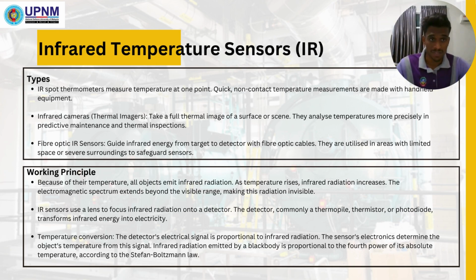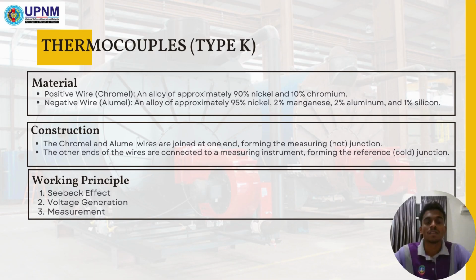Now let's not get deep into it because there's another important transducer which we're going to use for the project. Now this is the transducer we're using for the project, the thermocouple type K. For the positive wire we are using chromel, an alloy of approximately 90% nickel and 10% chromium. And for the negative wire we are using alumel, which is 95% nickel, 2% manganese, 2% aluminum, and 1% silicon. The construction is that the chromel and alumel wires are joined at one end forming the measuring hot junction. And for the working principles, I will let my partners explain it.